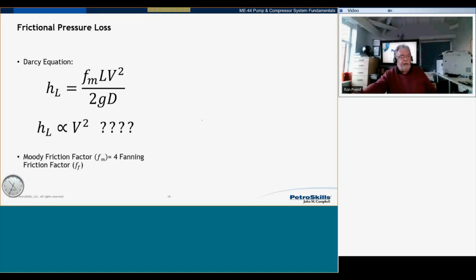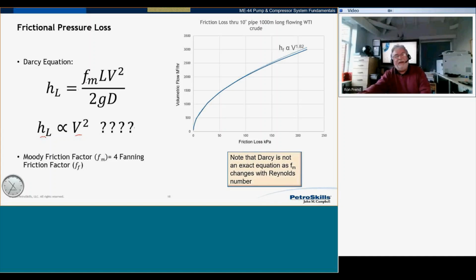I think a lot of us have heard about this thing called the affinity laws. And one of the affinity laws says that the friction head loss is proportional to the square of the flow. Now, if you look at the formula, that starts to make a little bit of sense. Remember Darcy? He said F times L over D times V squared over 2G. So really, it looks as if the friction head loss is proportional to the square of the velocity. No, it isn't. Because remember that the Darcy is not an exact equation, as that Fm changes with the Reynolds number. We just saw that on the Moody chart.